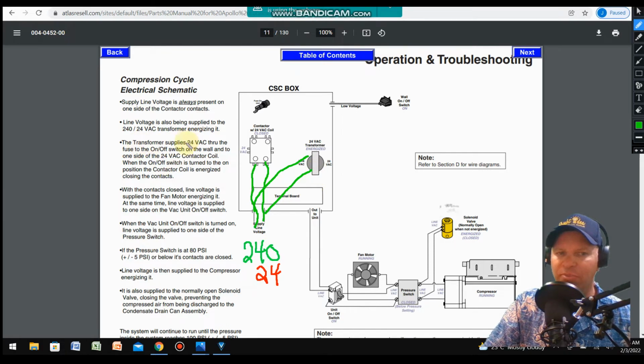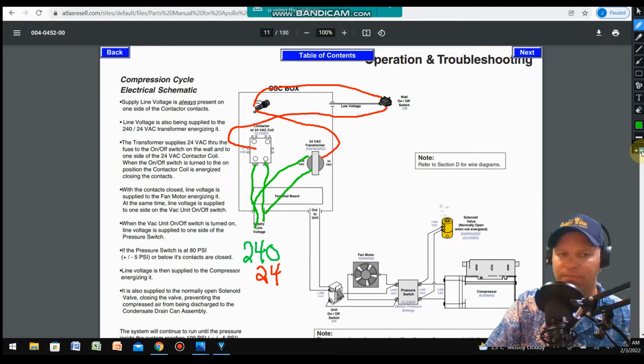Now, the transformer supplies 24 volts through the fuse to the on-off switch on the wall and to one side of the 24 VAC contactor coil. What that looks like is this. We have the voltage going through the fuse to the switch, and then from the switch to one side of the coil. Now, when the on-off switch is turned on, the contactor coil is energized, closing the contacts. The other side of the transformer goes to the other position here. So you have 24 volts controlling 240 volts.